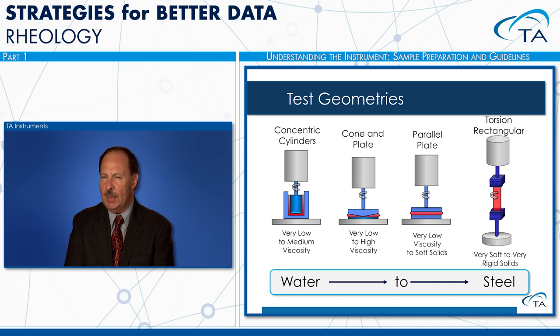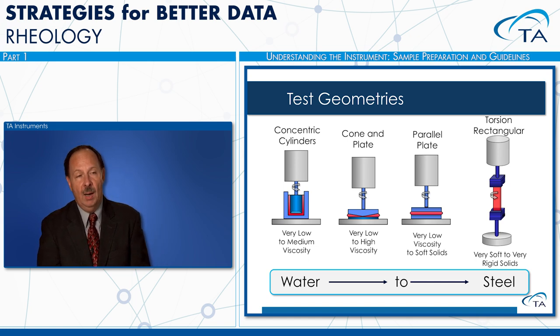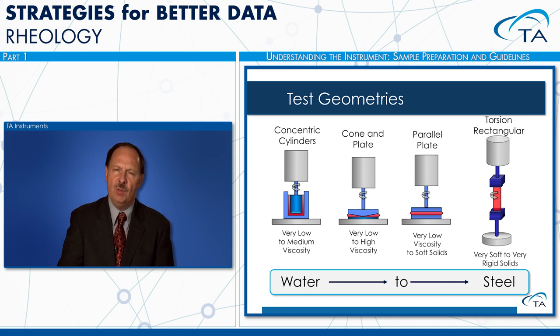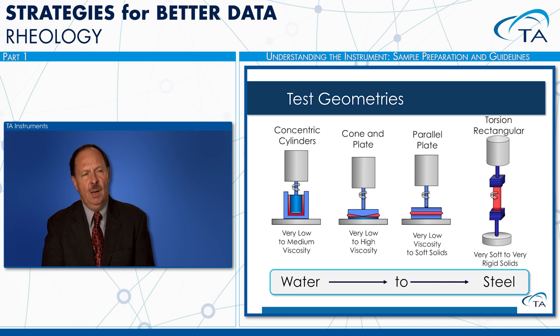They all have great usefulness, so that's why we sell different versions of these. And as we like to say, with a single rheometer, you can go from everything from water to steel, and that's assuming that you have the right geometries. So on the left here, we have a concentric cylinder geometry, and this is used primarily to test coatings, paints, and materials like that.